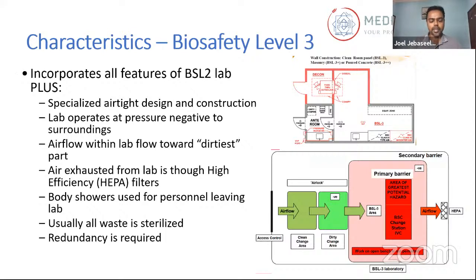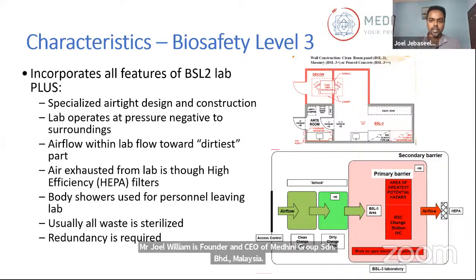A bit more on BSL level 3. BSL level 3 will be an add-on on BSL level 2. So you need to have everything that you have in BSL level 2, plus you need to have airtight construction. The lab must work under negative pressure. So there must be at least minus 15 Pascal between each entrance point that you see here. You need to have an autoclave. Nothing leaves the lab before it is sterilized or in a sealed container that you can take off site for further decontamination. Right? So those are some of the critical areas in BSL level 3.